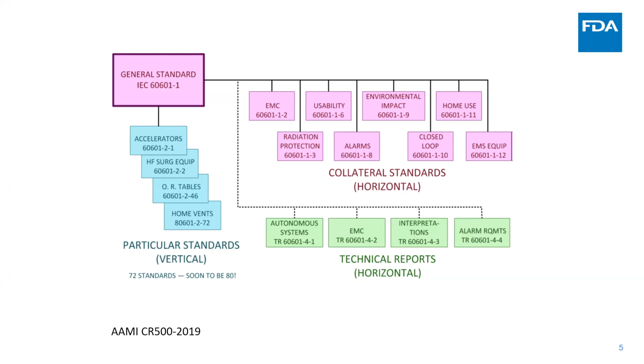These add additional, usually more conservative requirements on the robustness of your device, particularly the EMS and the home use. They talk about shock and vibration so that your device actually survives after you drop it on the floor, for example, or if you're bouncing around in the back of an ambulance. And EMC, electromagnetic compatibility: if you bring your cell phone right next to the front end of many of the physiologic monitoring devices, there's enough energy put out from your phone that it completely obliterates any signal you might get. Right? So that has to be handled, and it is handled by this series of standards.